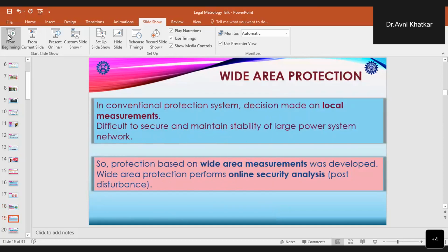When we talk about wide area management, wide area protection also comes into the picture. Initially in conventional protection systems, all the decisions were made on local measurements. Because of these local measurements, it was very difficult to secure and maintain the stability of large power system networks. So now, protection based on wide area measurements was developed so that we can have a wide area protection system which can perform online security analysis, and we can also have a post-disturbance analysis of the complete system.